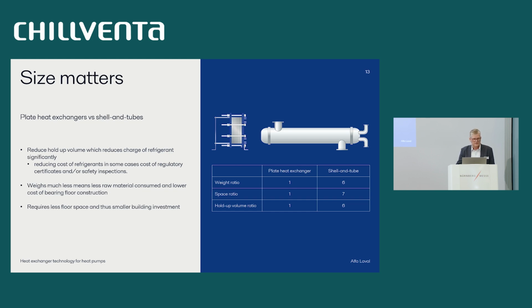We will reduce the volume of refrigerant, which reduces the cost of refrigerant. If you have natural refrigerants, they are not so costly, but it's good to reduce because you can get under various regulatory certificates and safety inspections in the various markets, depending on the rules. The weight is also much lower, and you can have less structure and floor construction, and it requires floor space to a minimum, which means you can have a smaller building investment. So there are many advantages.